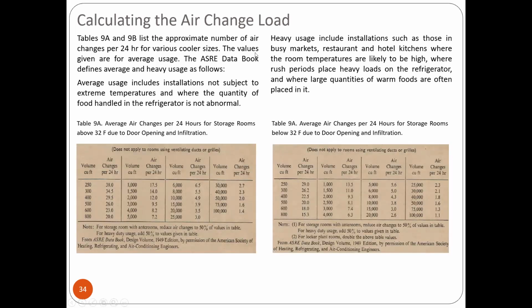So table 9A and 9B list the approximate number of air changes per 24 hours for various cooler sizes. So ito naman is may volume, makukuha mo na yung air changes per hour. Okay? Mga shortcuts. So kapag detailed, so doon ka sa mga sa una nating discussion. So the values given are for average usage. So the ASHRAE data book defines average and heavy usage as follows. Average usage includes installations not subject to extreme temperature, and where the quantity of food handled in the refrigerator is not abnormal. Heavy usage includes installations such as those in busy markets, restaurants, and hotel kitchens, where the room temperatures are likely to be high, where loads place heavy loads on the refrigerator, and where large quantities of warm food are often placed in it. So ito yung isa, table 9 is above 32 Fahrenheit, and ito naman is below 32 Fahrenheit.